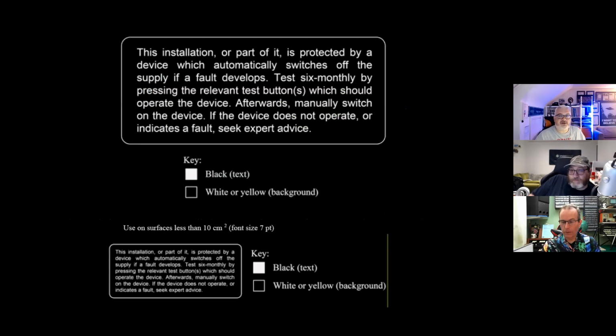The installation, or part of this installation, is protected by a device which automatically switches off the supply if a fault develops - test 6 monthly. Now, I completely disagree with this, and anyone commenting on this, it needs to just say test at a frequency recommended by the manufacturer. Fusebox require monthly, ABB require 12 monthly - or just put 'test periodically', something, or leave a space for you to write in the time.